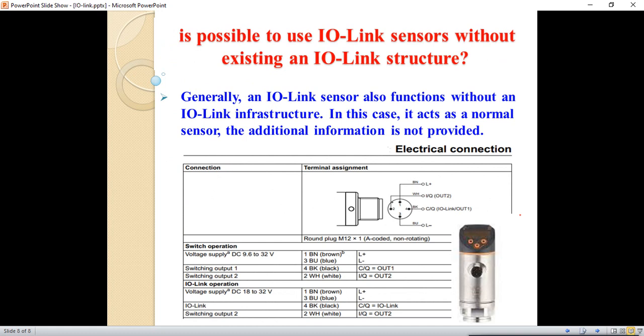Is it possible to use IO-Link sensors without an existing IO-Link structure? Yes, this is another advantage of the IO-Link technology. Sensors or actuators that have the IO-Link feature can be used on another network that doesn't have IO-Link. Generally, IO-Link sensors also function without an IO-Link infrastructure — in this case they act as a normal sensor, and the additional IO-Link data is not provided.